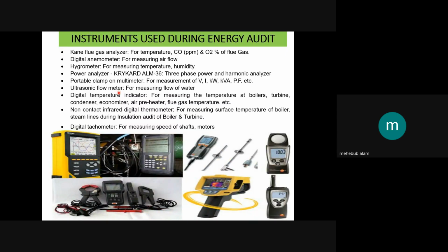During an energy audit, several types of instruments are used for measuring and collecting different types of data. In the case of motors, we have to collect the voltage, power factor, how much ampere is being taken, and how much power is being consumed. There are so many mechanical equipment, pumps, so we have to measure the pump flow and air flow also. That is done by the digital anemometer, hygrometer, power analyzer, portable clamp multimeter. An ultrasonic flow meter is required for measuring flow of the water for the various pumps.